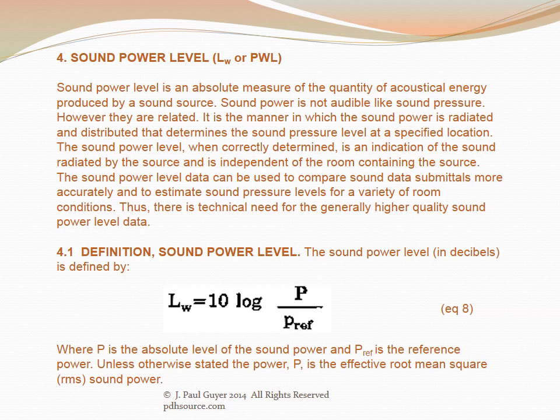Sound power level is an absolute measure of the quantity of acoustical energy produced by a sound source. Sound power is not audible like sound pressure, but they are related — it is the manner in which sound power is radiated and distributed that determines the sound pressure level at a specified location. The sound power level, when correctly determined, is independent of the room containing the source, and sound power level data can be used to compare submittals and estimate sound pressure levels for a variety of room conditions.